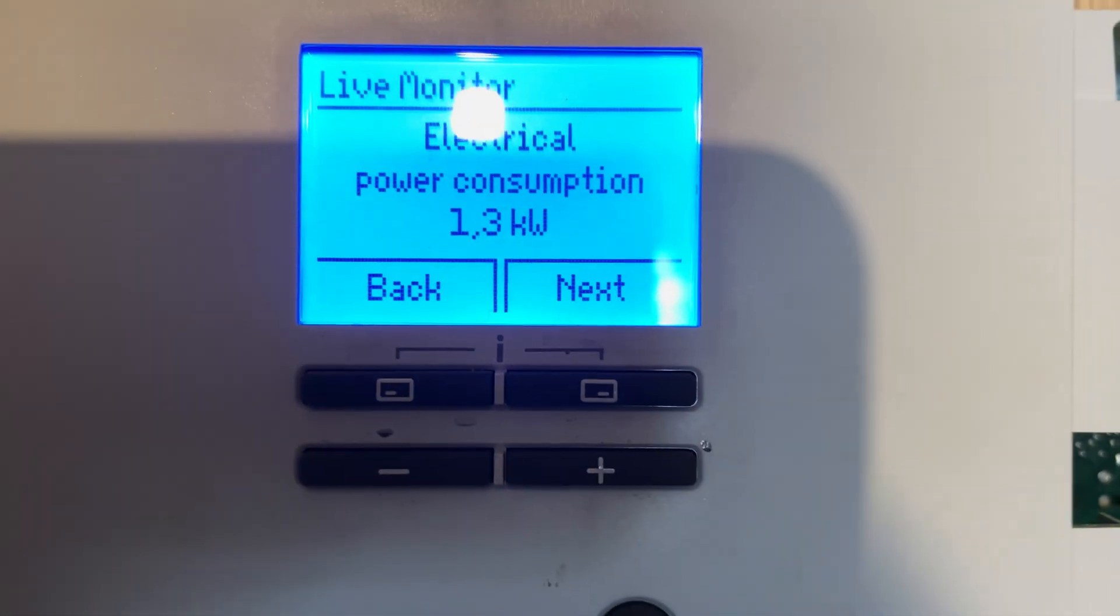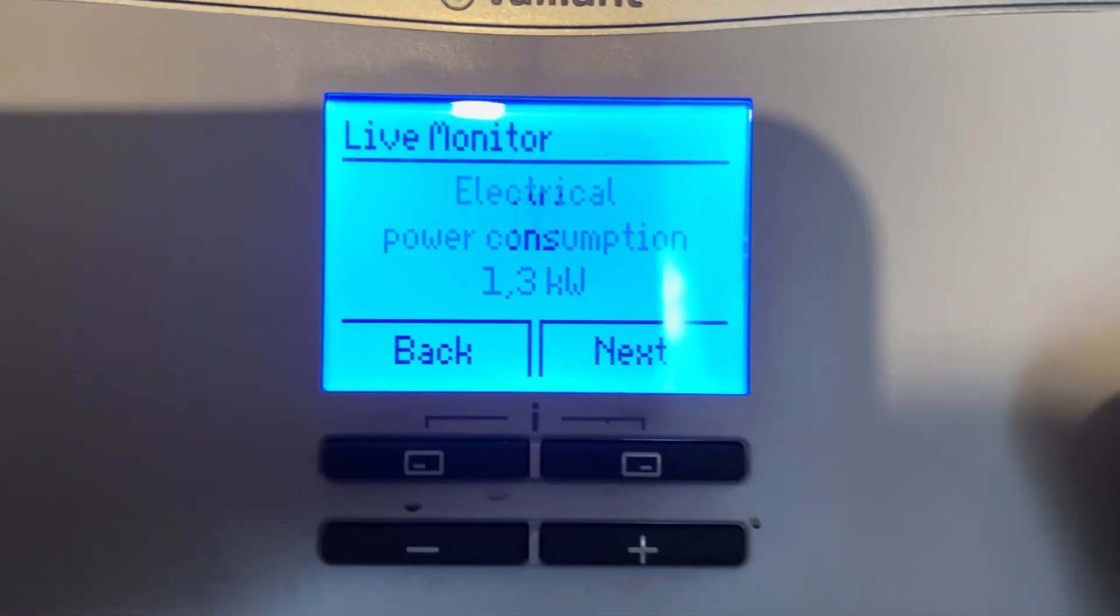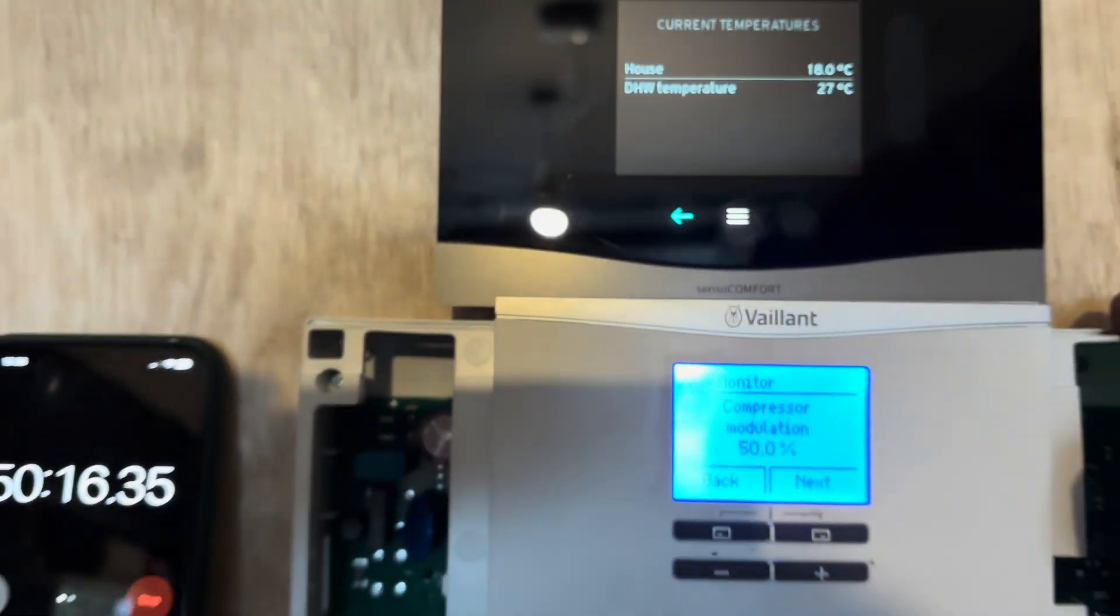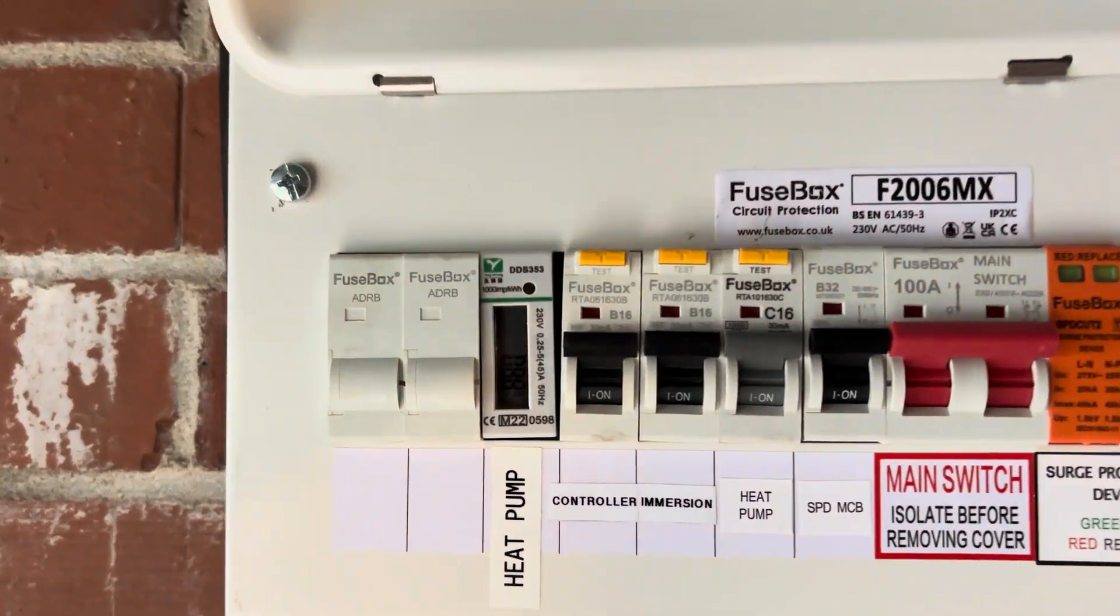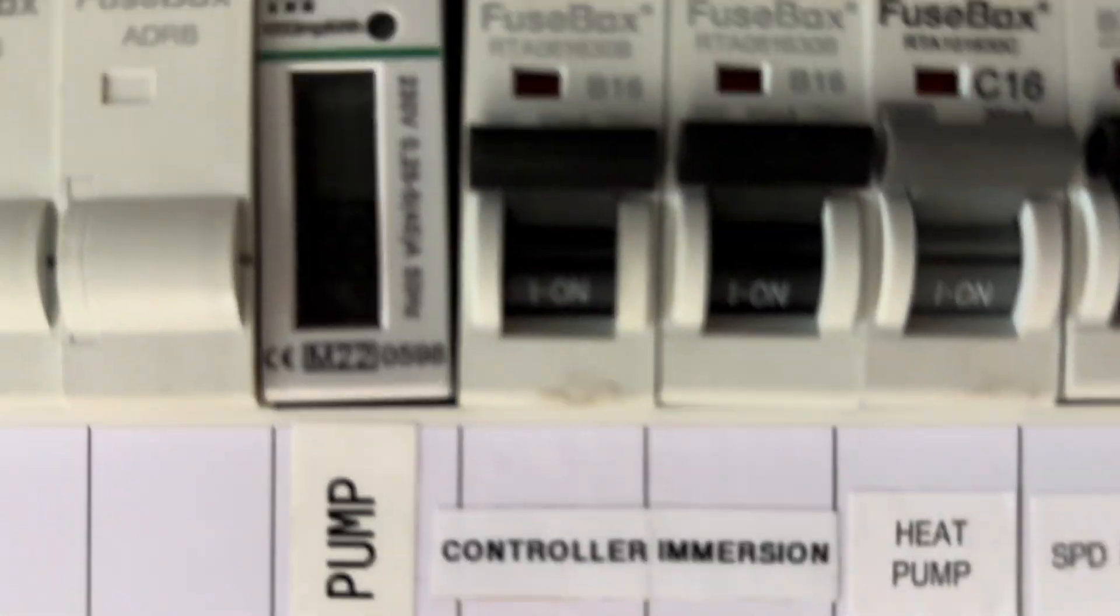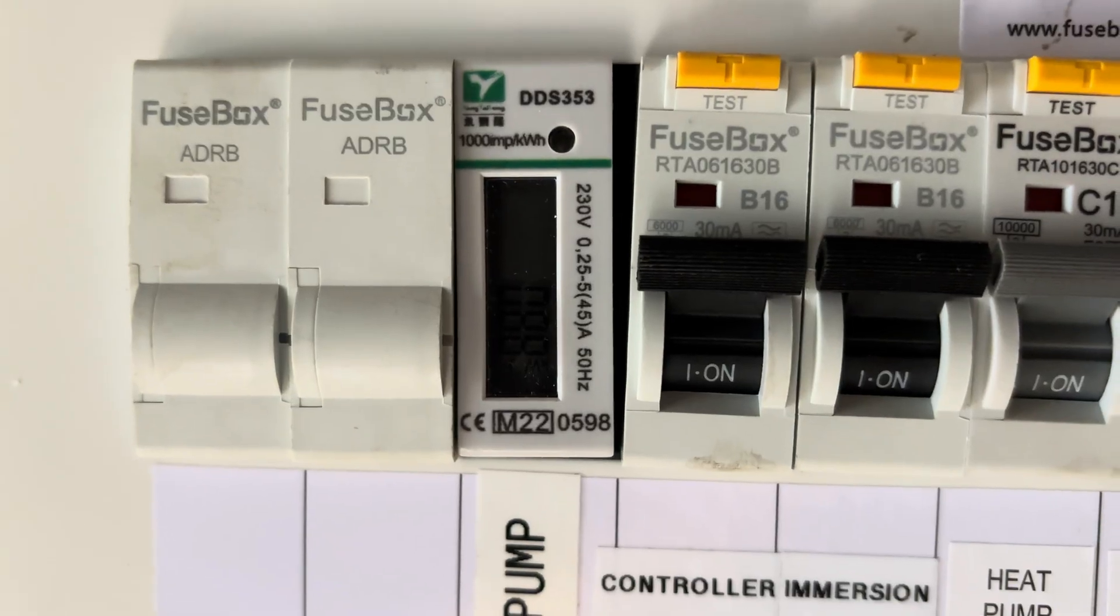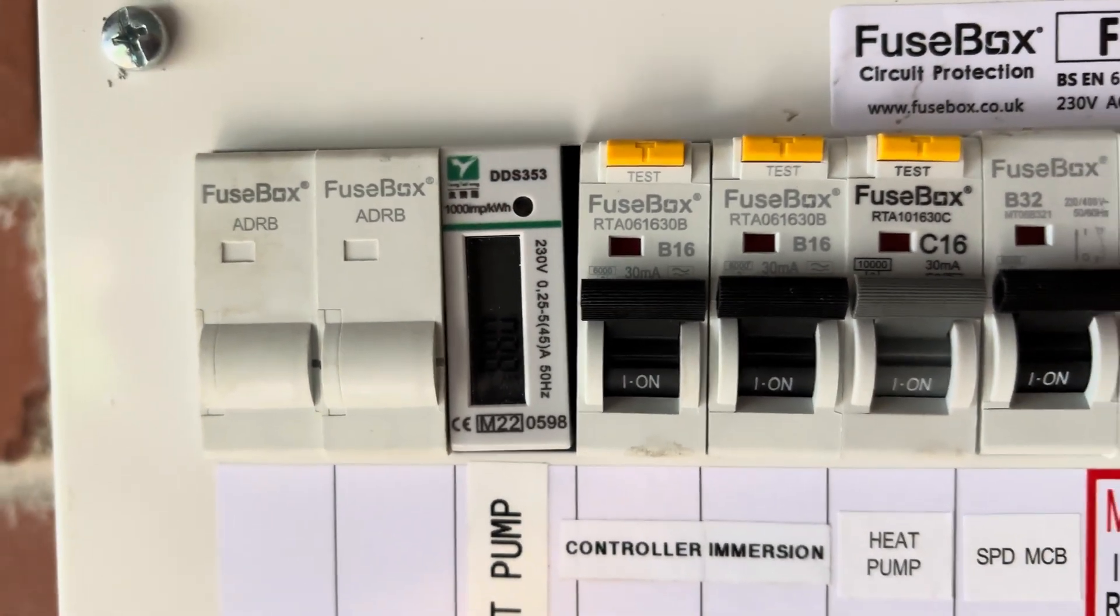50 minutes in now. We're up to 27 degrees C. Electrical consumption, 1.3. Compressor modulation still 50%. Looking at the meter now, we have consumed 0.88 kilowatt hours so far or 880 watt hours. Not bad.